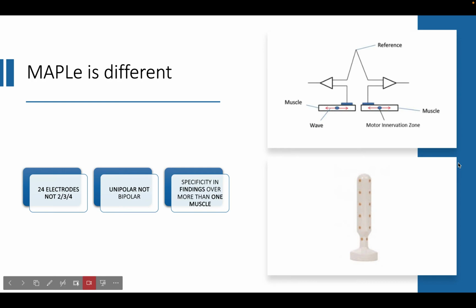It works in a unipolar rather than a bipolar method of function. Now, unipolar, as you can see from the top right image on your screen, will have an electrode on different muscles. So each muscle will have its own electrode. And those electrodes, instead of comparing findings with each other and sending that information to a machine or a screen, these electrodes with the Maple compare their findings with a zero reference point. So the reference point is an EMG electrode that would sit on a bony part of the body, say the ASIS, the patella, or the medial or lateral malleolus.